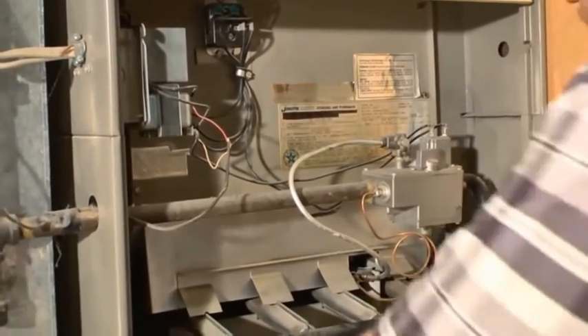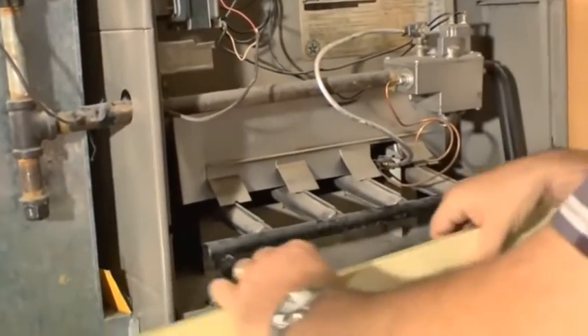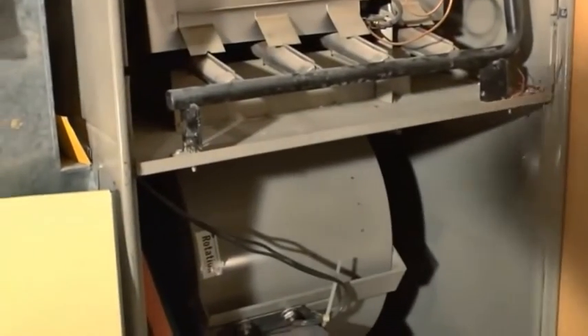Take a look at the fan on this. This is an upflow furnace, with our fan sitting down on the bottom here. Let me grab my flashlight. Looks like we have a little bit of an issue here. The filter has been sucked into the pulley of the motor. It's actually riding up against both pulleys.